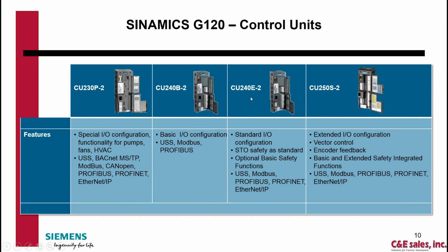Then we get up to the CU240E-2. E is where Ethernet would come in potentially, or some other industrial networks. Again, with USS, which is a Siemens serial network for drives that has been pretty low speed, or Modbus, Profibus, and then Profinet or Ethernet IP, where your Ethernet flavors come in. Then the CU250-S also brings in the capability of closing the loop from an encoder for speed loop. So you can get closed loop vector control, as well as some basic positioning with this control unit.